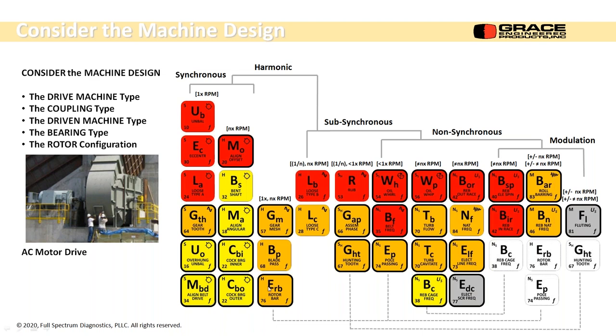So I have an AC induction motor. I can get rid of DC electric problems and fluting. You might not know what fluting is. It's electro erosion of the raceways in the bearing from discharges of either current or voltage. So if this was a DC motor, that occurs sometimes. On AC induction motors on variable frequency drives, it can also occur. But if it's just an AC induction motor, usually it's electrically pretty good, and you'll never get the erosion problems.